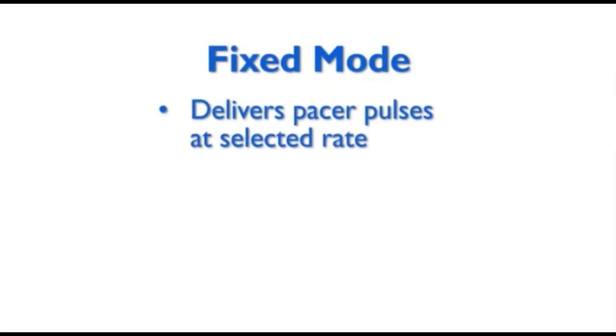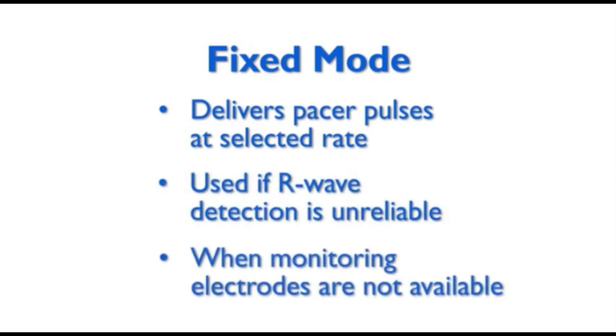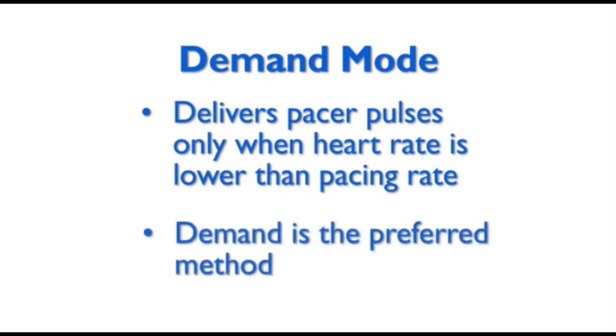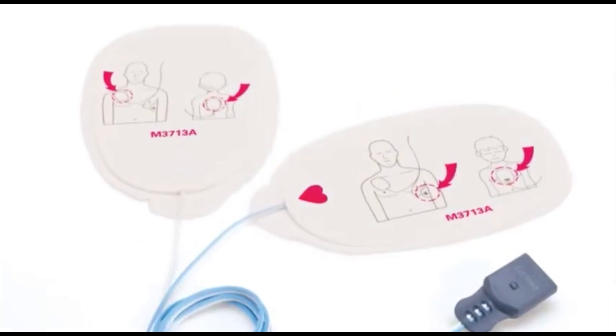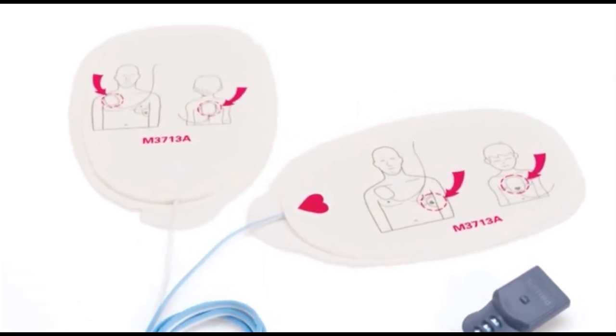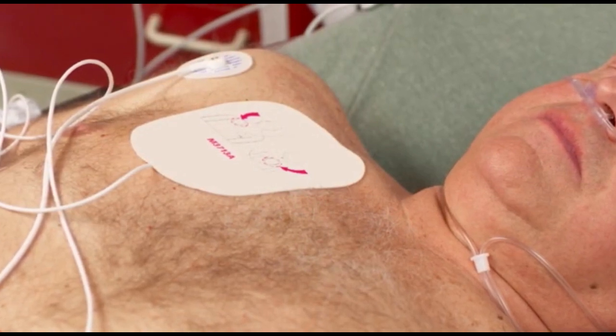In fixed rate mode, the pace rate is set by the clinician regardless of the patient's intrinsic heart rate. This option is preferable when the ECG signal becomes extremely noisy due to motion artifact or when the pacemaker is sometimes unable to sense the intrinsic beat. Another reason for using fixed rate mode is to terminate tachyarrhythmia by overdriving the patient's intrinsic beat. This method has been successful in a limited number of patients.